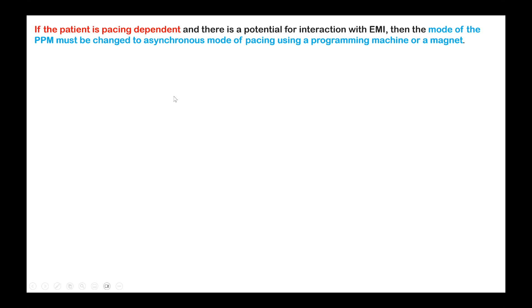Okay. So converting, earlier it would have been only when there is a delay or the failure of inherent contraction, then the pacemaker will be stimulating the heart at the time. That is the way it is programmed. But once you put the patient under anesthesia, you remove that demand type and make it compulsory stimulation at a particular rate, so that the risk of bradycardia and hypotension is prevented. Okay, that is how it can be programmed.